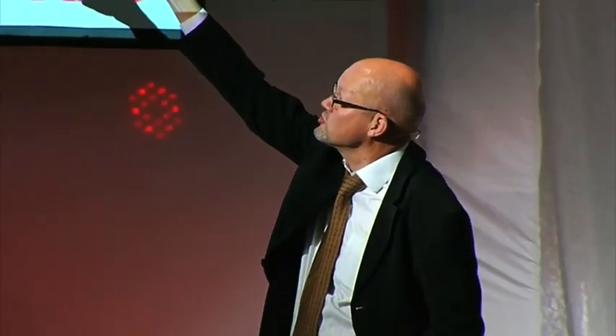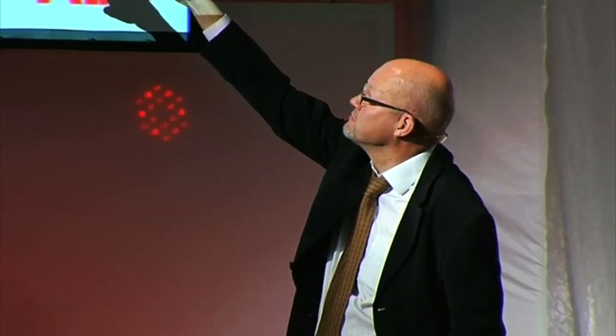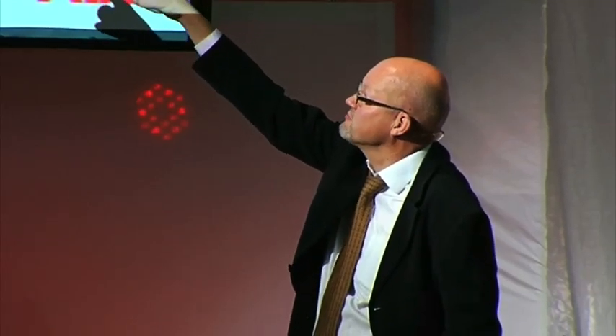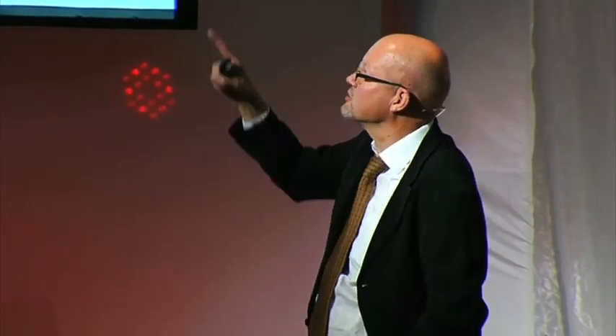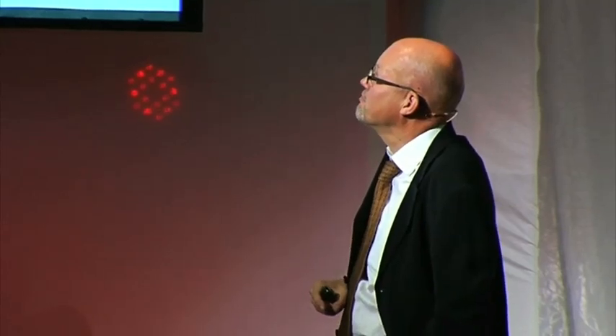Well, our target was to get some 5 kilohertz frequency on this transformer, and if you see on this graph, we have the red cross at 50 hertz. If you have a 50 hertz transformer, a typical ABB distribution transformer that we sell to our customers, it's not power density, it's the opposite: how many kilograms per kVA it weighs. We see it is about 2, so for 1 megawatt, that's 2,000 kilograms of transformer.